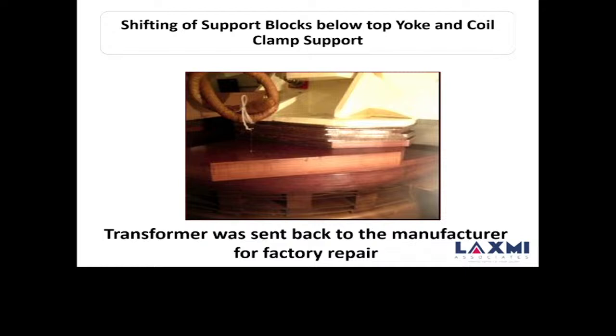Based on that, the transformer was opened for inspection before detailed commissioning. Once it arrived at the site and we suspected this was a problem, it was opened for inspection, and what you see here is that the clamping support structure has already shifted. It's not in a normal position. That was one indication. The other indication was that a lot of nuts, bolts and structures were loosened from inside.